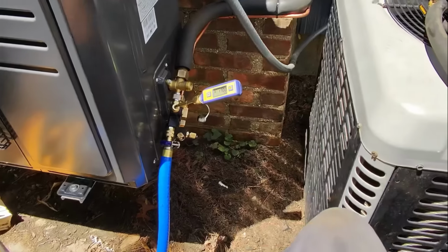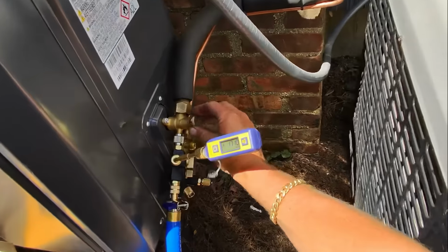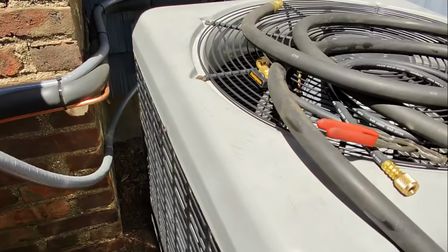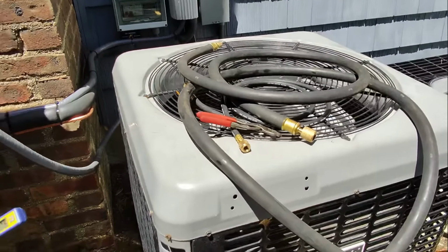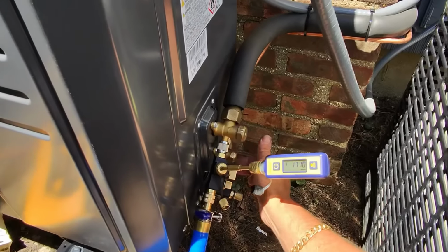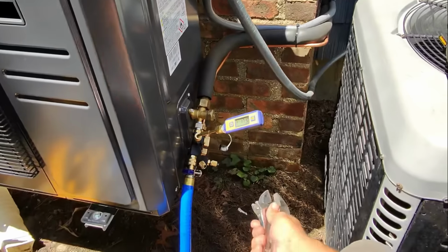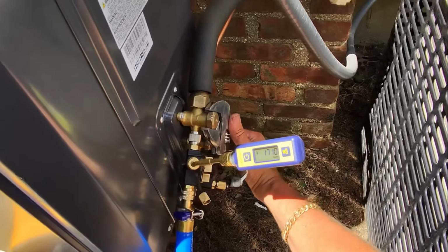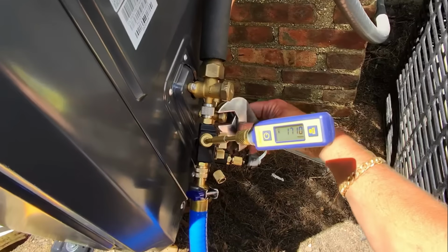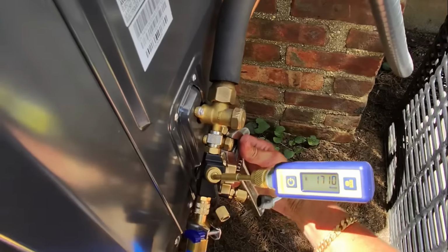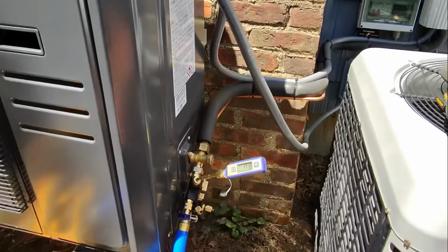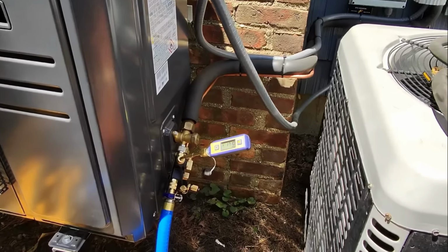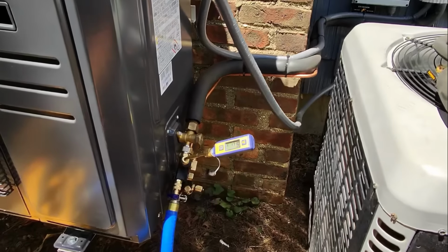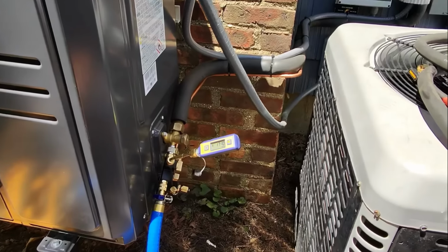No bueno. All right, I vacuumed down the system. She stayed around 480 microns for about 2 minutes, and that passed the decay test for me. Got all the moisture out of the system now. I opened up the service valves, my high side first and then my low side. And we're ready to fire up.